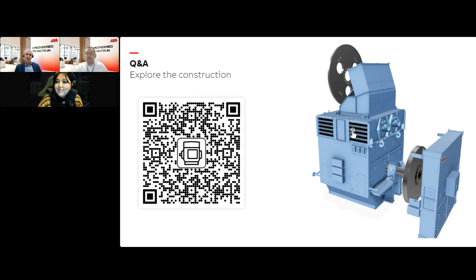Maybe I take this one. Typically these power plants are in non-hazardous areas. The prime mover is usually an engine, and normally these are installed in a safe area only. So typical power plants, balancing plants, power plants for oil and gas outside the actual hazardous area, mining not in the mine but in a separate power plant where the gensets are located. So in summary, yes, these are intended mainly for the safe area, not the hazardous classified area where there might be gases present which could ignite.